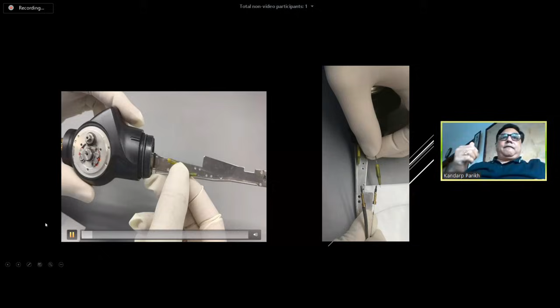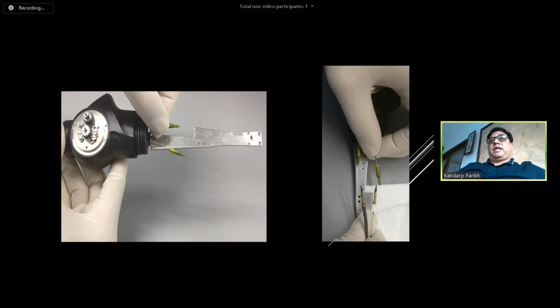This is very important for us to understand. The reason is that after several uses of the ureteroscope, the deflection is hampered: from 270 degree it will go down to 220 or 180 degree. In such a case, if you send this ureteroscope for a repair, simply the company has to open up this handle, tighten this wire, and again snap it here, so that you will prevent a major damage to your scope and major reparation. But if you break this wire by producing a lot of pressure at the deflection lever, in that case, it will go beyond repair, or it will cost you a lot of money. So I think for you, this is very, very important to understand.